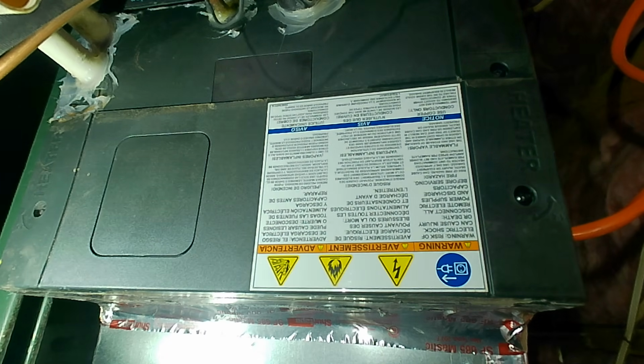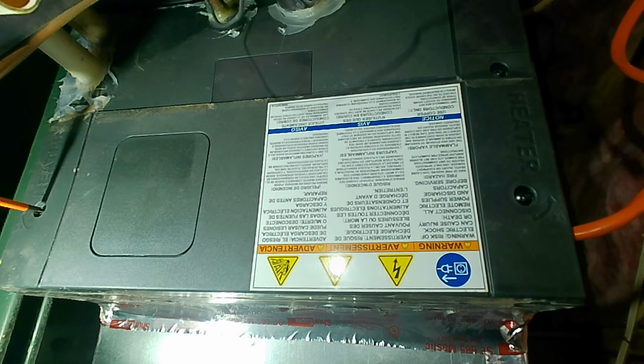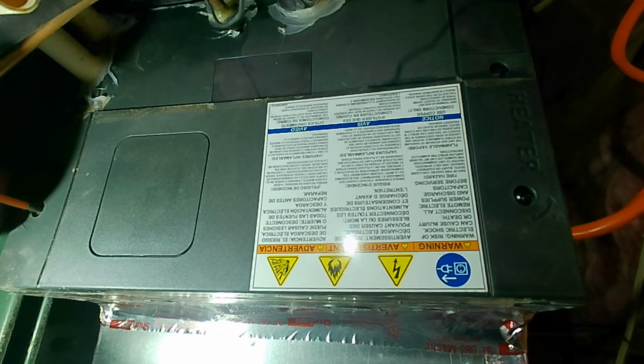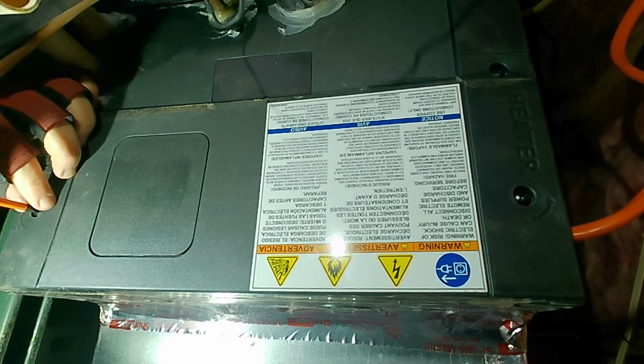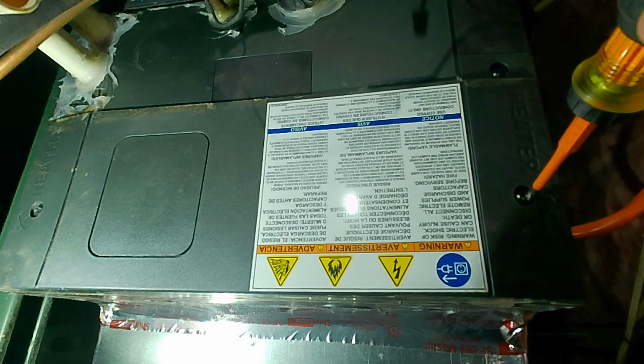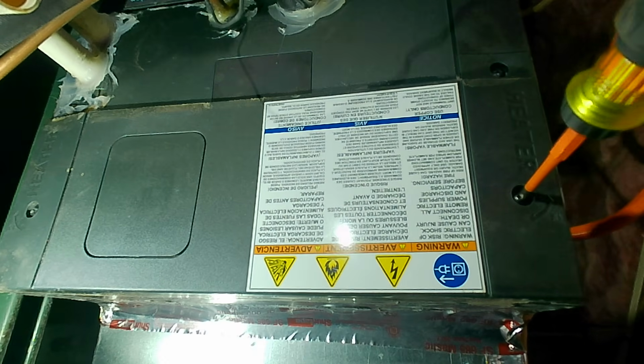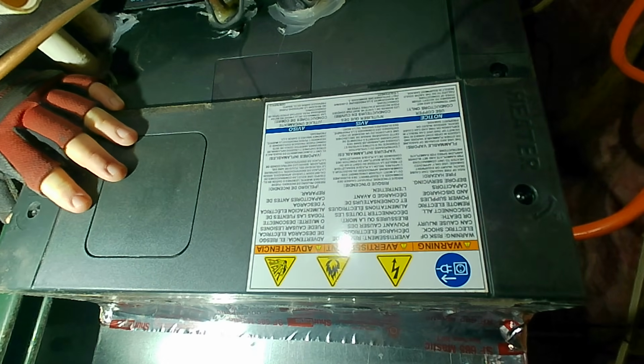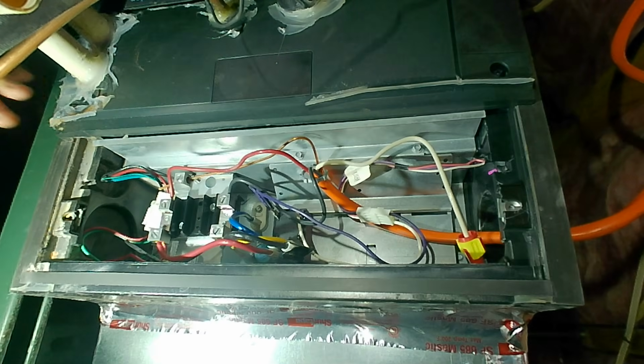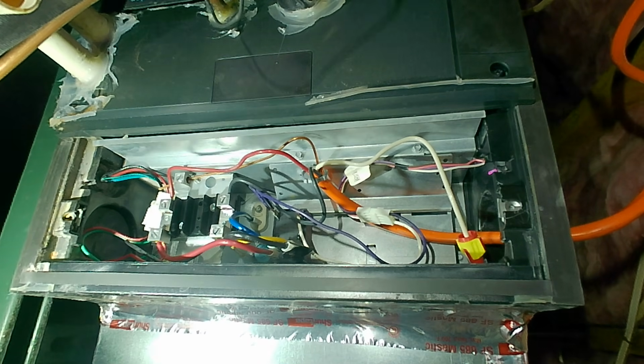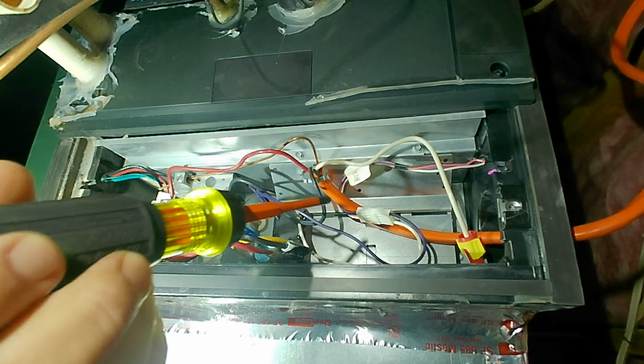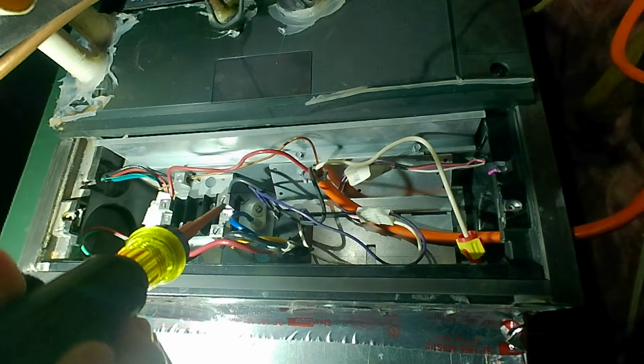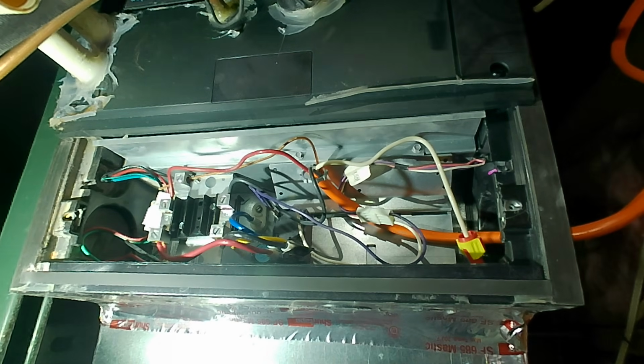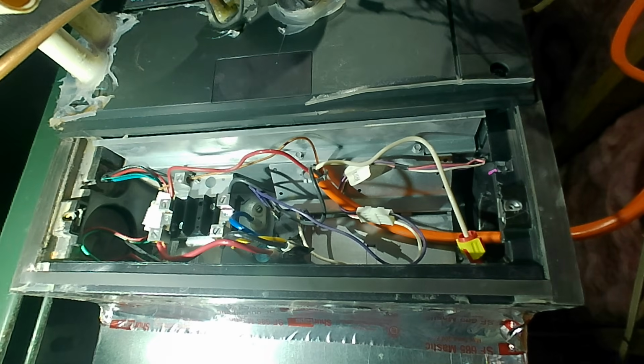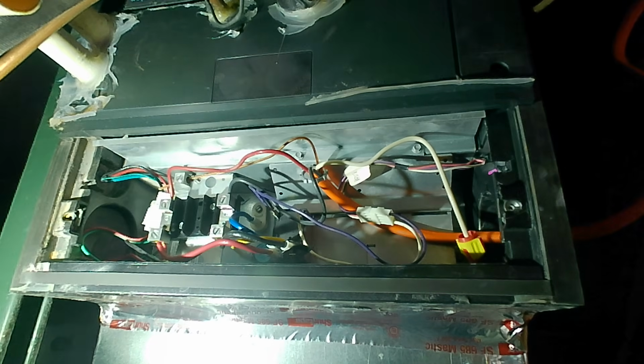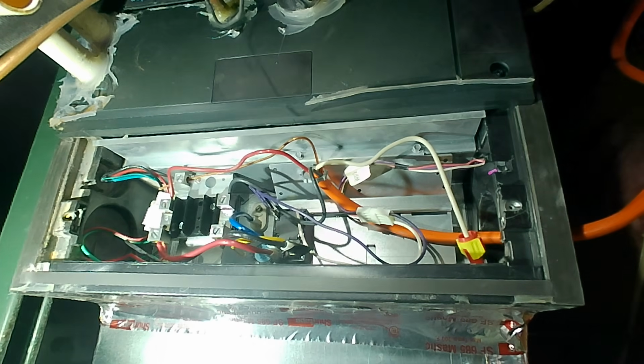We've had an issue with the high voltage limit going out on these, and come to find out they're one-shot limits, which means they trip. They're not resettable. They don't automatically reset. They're one and done limits. So when they go out, what we've been finding is we come back, put a new limit in it, and not long, 10-15 minutes of runtime, that relay has been sticking closed.